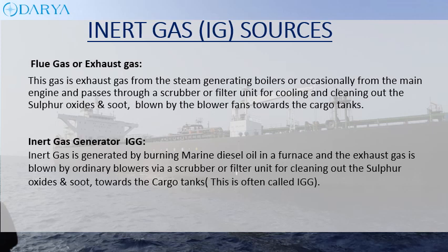Inert gas can also be generated by burning marine diesel oil in a furnace; the exhaust gas is blown by ordinary blowers via a scrubber or filter unit for cleaning out the sulfur oxide and soot to the cargo tanks. This unit making the inert gas is often called IGG.